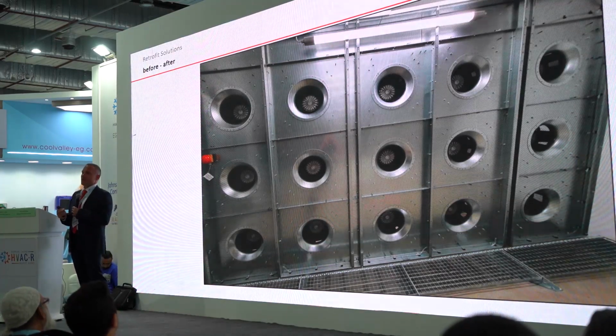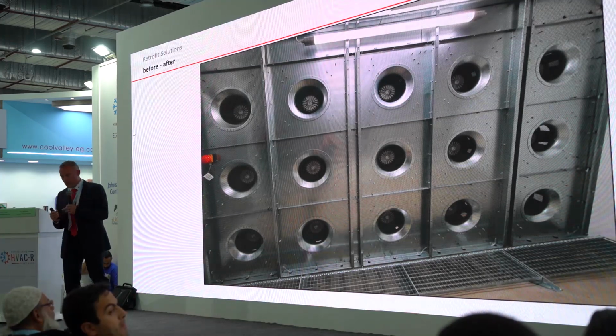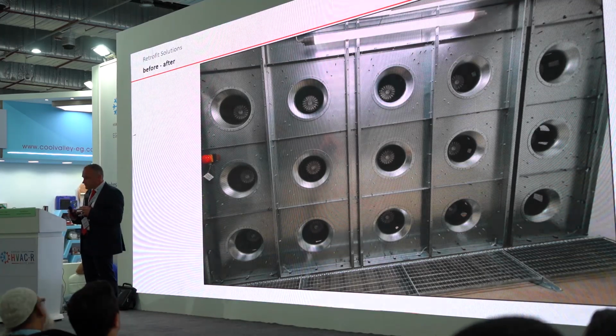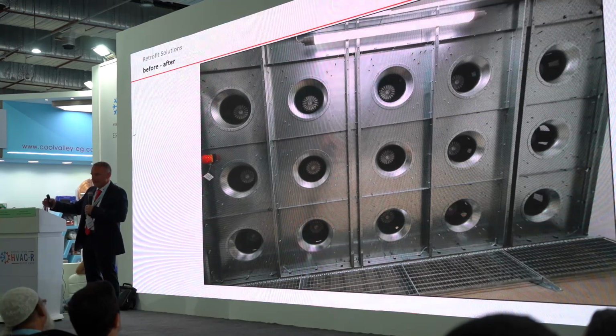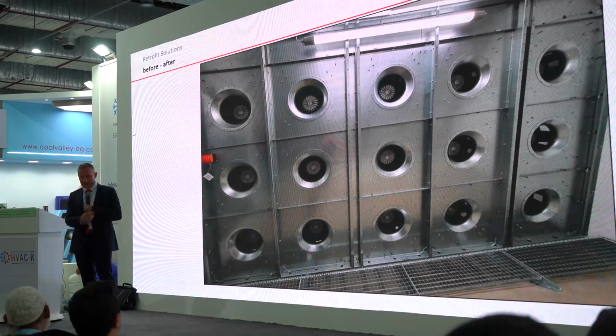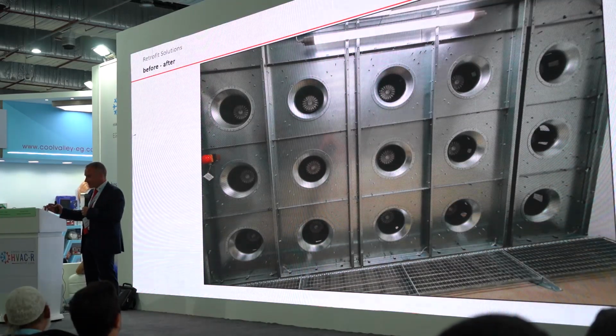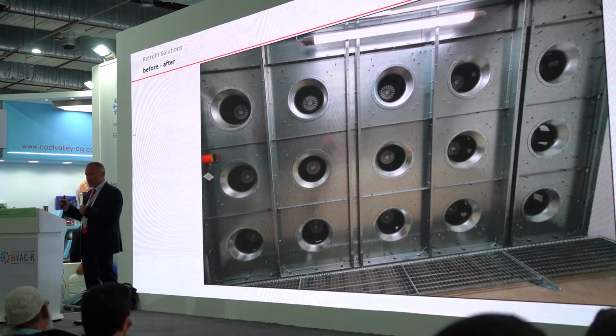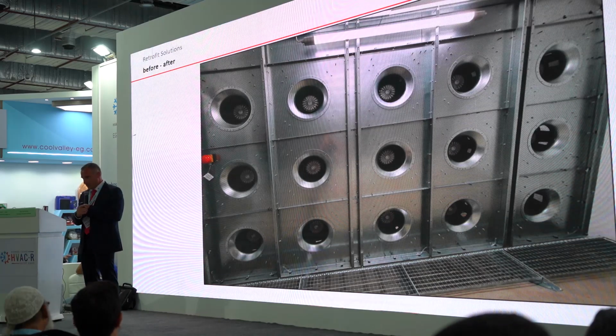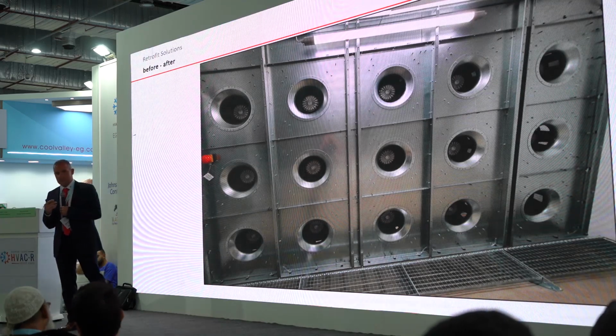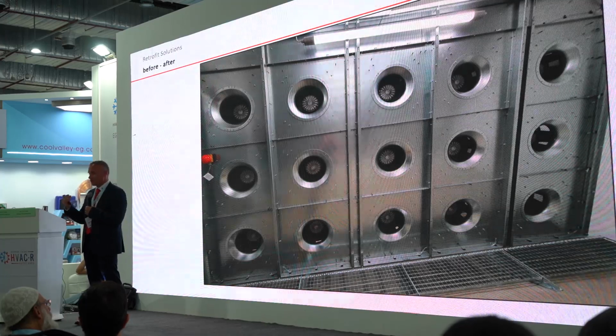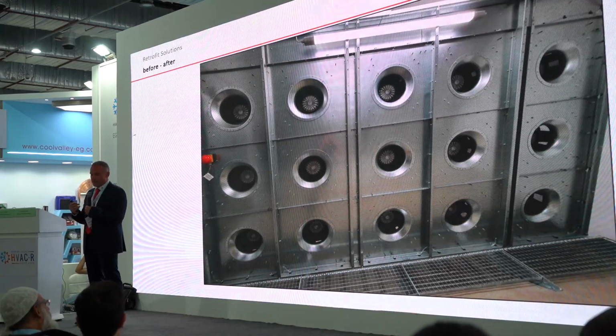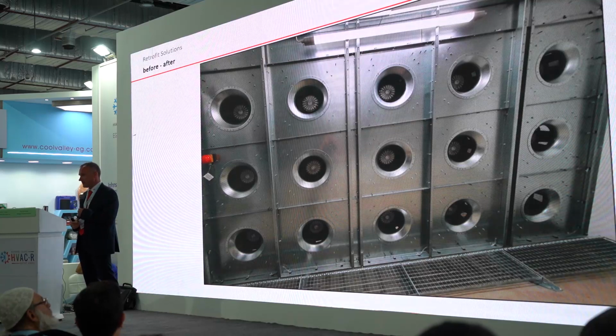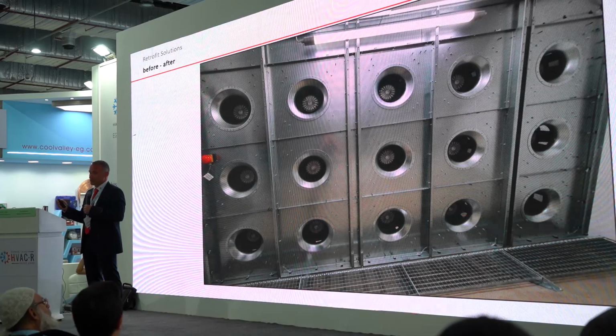Well, here you see an EC fan grid. Imagine you replace an old belt-driven fan, maybe 2, 3, 4, 5 meters in length depending on the power, with an EC fan grid, a fan wall. The maximum is 450, 500 millimeters. So you save a lot of space in a new air handling unit as well as in an existing one. If you think about putting in better filters or more filters or heaters or coolers, and you need more space inside, the space is available if you go for an EC fan grid. Depending on the size, you will win 1, 2, 3 meters.